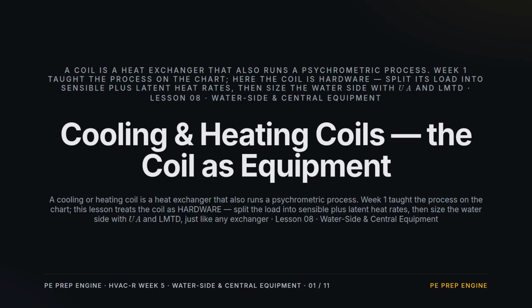Week 5, Lesson 8, Cooling and Heating Coils. The coil as equipment. In Week 1, you saw the cooling coil as a process on the psychrometric chart. Now we treat it as hardware, a heat exchanger with air on one side and a working fluid on the other. We split the load into sensible and latent, then size the water side with UA and LMTD.